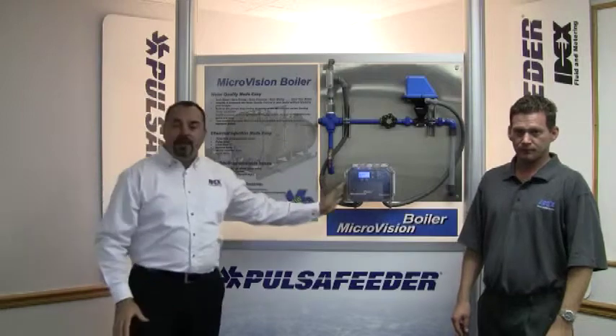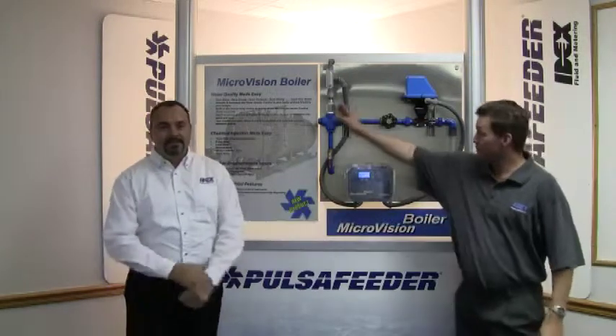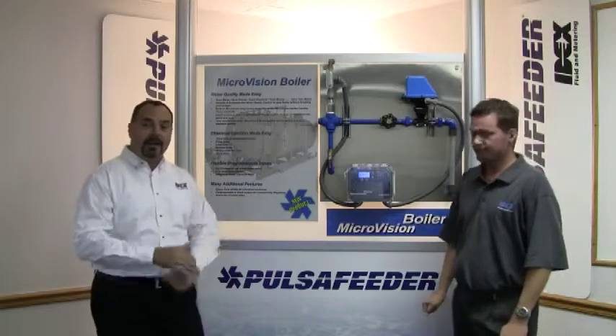In this video, we're going to review the features and benefits of the MicroVision Boiler, including helpful information on the setup and operation, which shows exactly how easy it is to use this controller in the field. Some of the key features of the MicroVision Boiler Controller are the rugged NEMA 4X enclosure. Standard temperature compensated probe is rated for 400 degrees Fahrenheit and 250 psi. And of course, the unit can be operated in non-temperature compensated mode.